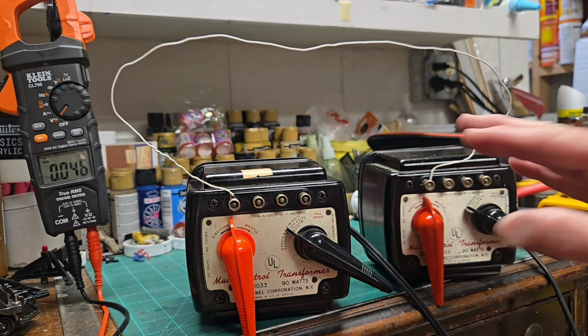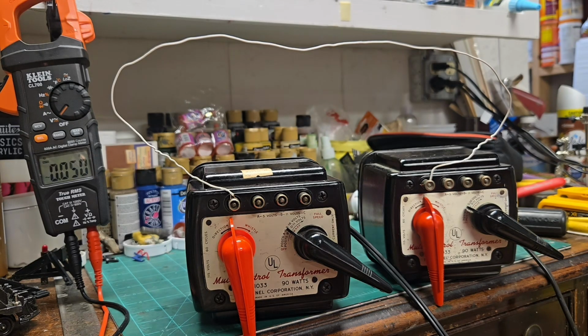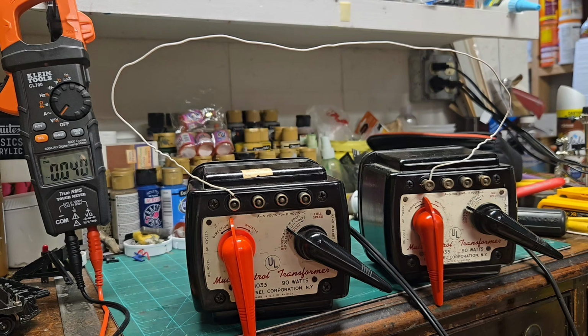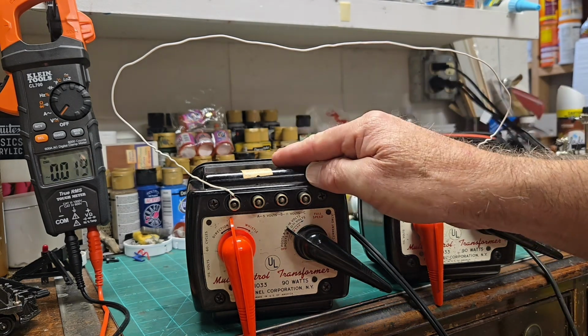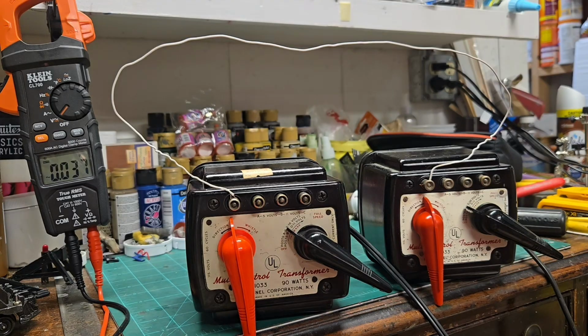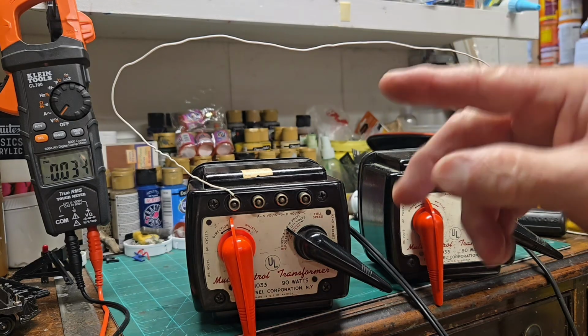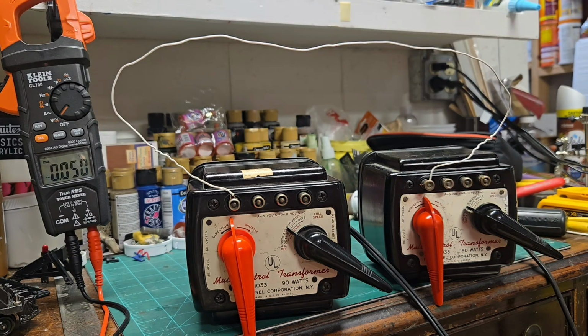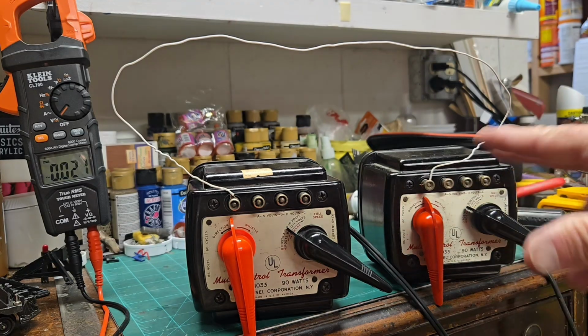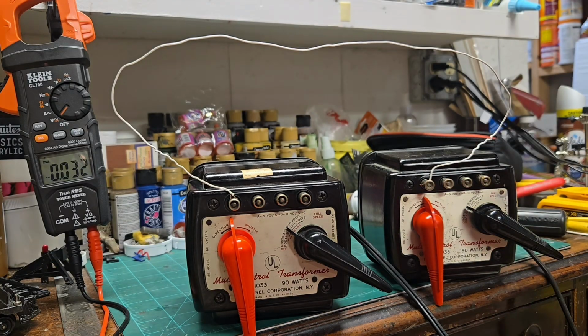So how do we change that if they weren't in phase? Well, you could swap these two wires. And when I talk to you about color coding, it could get you in trouble. This is why I phase my transformers with my CW80, because it does have the polarity corrected on the version I'm using. My black wire is my black wire, my red wire is my red wire on that transformer. That's why it's good to have your CW80s.